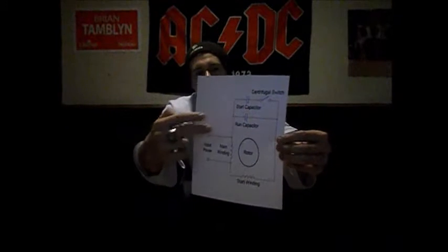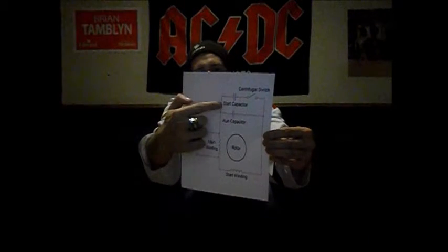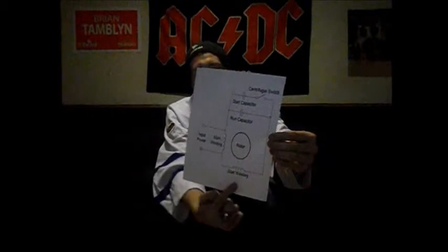Hello. As Joel stated earlier, I am here to talk about a type of induction motor, the capacitor run start motor. And basically what that motor is, as you can see here, is two capacitors, a start capacitor and a run capacitor, both in series with the starting winding. And what that does is it actually chokes the current coming in enough to give us a 90-degree phase shift. And that phase shift is enough to give us 200 to 325% more starting torque, which is great. That application right there is used in vacuums, washing machines, any small appliance.